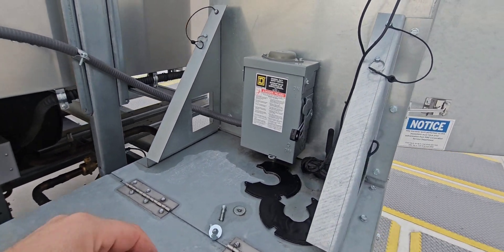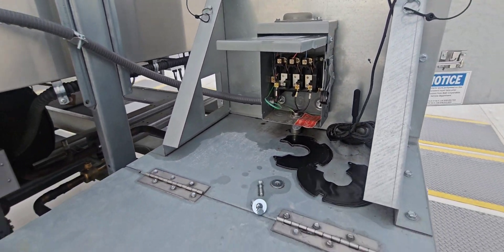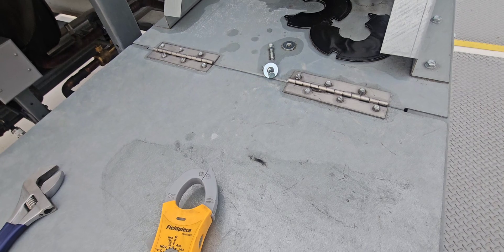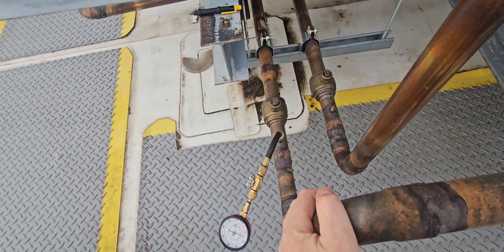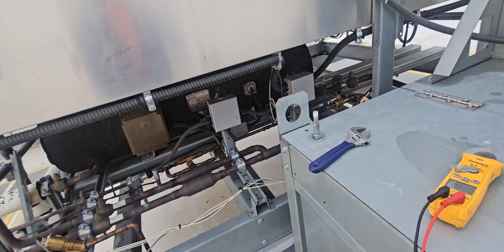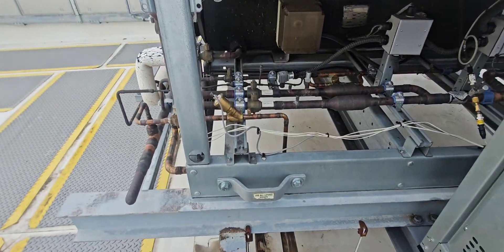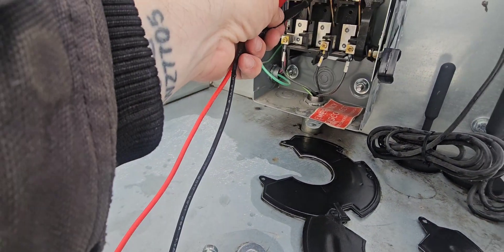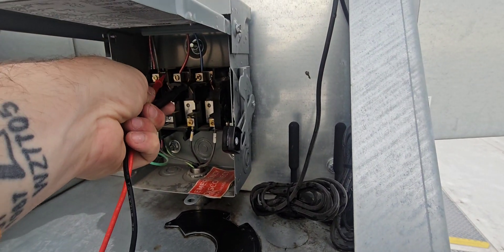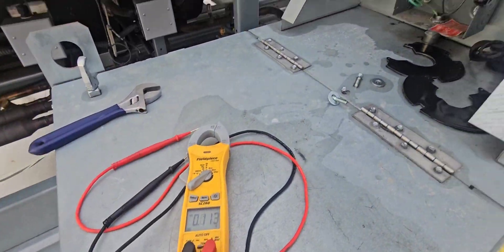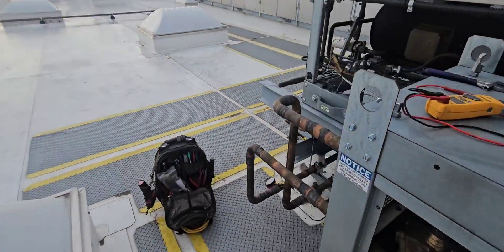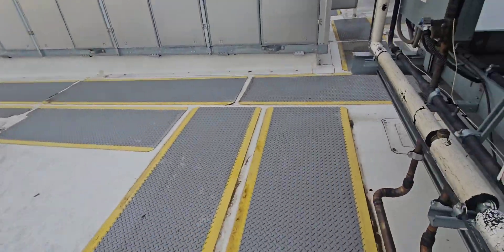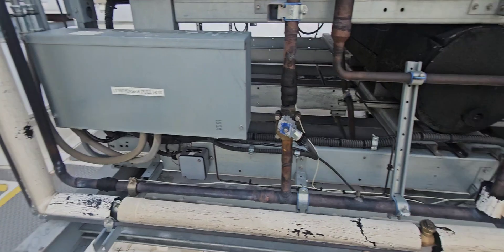I know I have power — actually, I don't know if I have power at this disconnect. Let me check — I checked the other one and had power but haven't checked this one. From my understanding, this one's never been turned on, but it's still maintaining liquid pressure. I checked and got nothing — no power on this. It says distribution panel 8, 10, 12 — that's for rack A. Liquid pressure is still maintaining, so I think it's just flowing through. That ball valve is turned off.